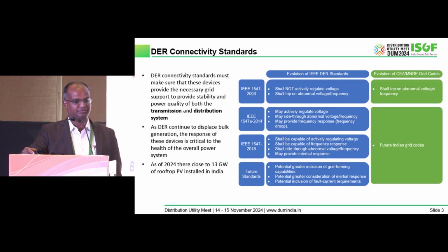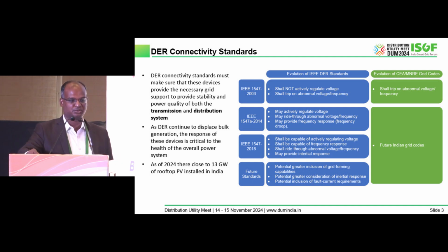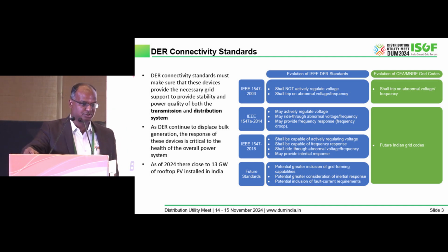As you can see on the left of that graph, you can see the different grid codes all the way from 2000. 2003 was the first IEEE 1547 kind of grid code, and then we did a big revision in 2014. The biggest difference is that in 2003 it was mostly about disconnecting from the grid if you saw a power quality, voltage, or frequency issue. By 2014 we modified that to actively regulate voltage, ride through some frequency issues, and provide frequency response if possible.